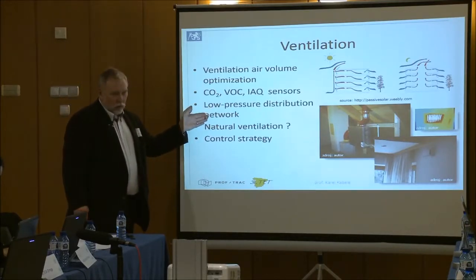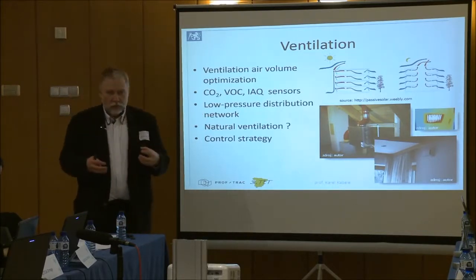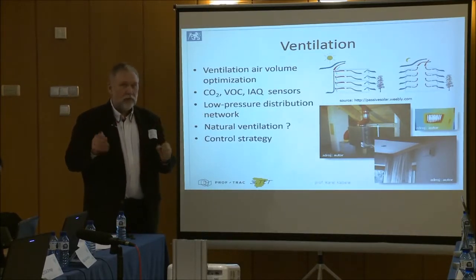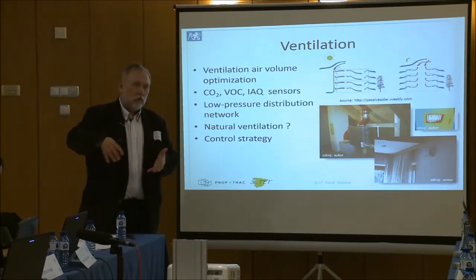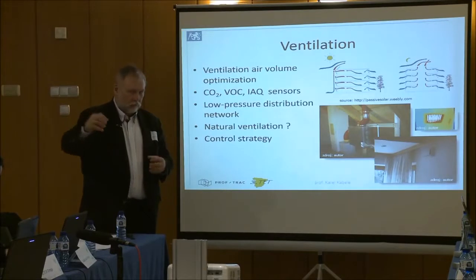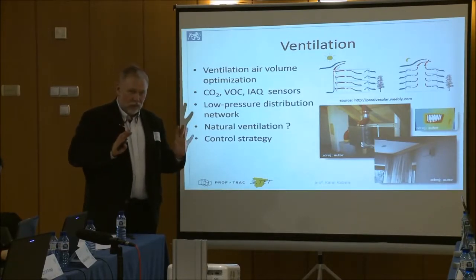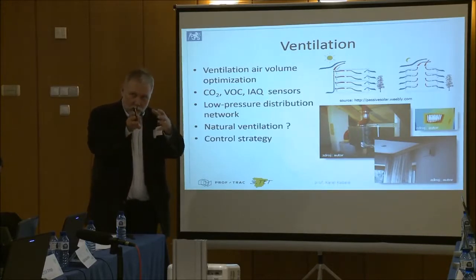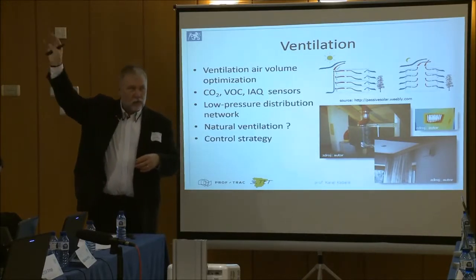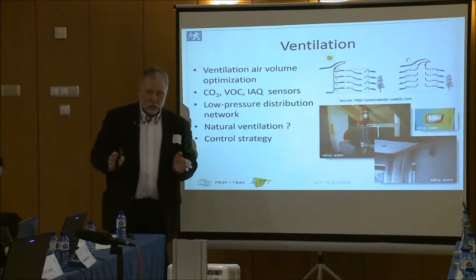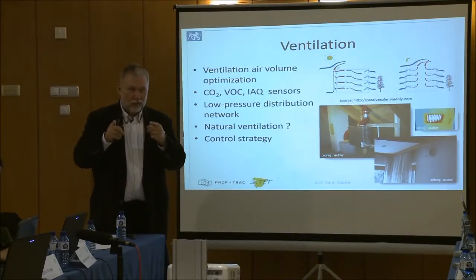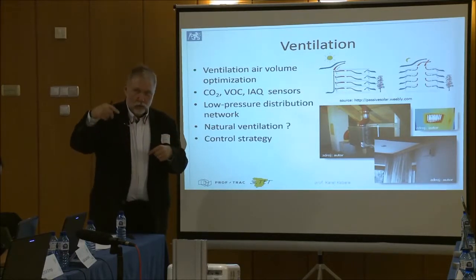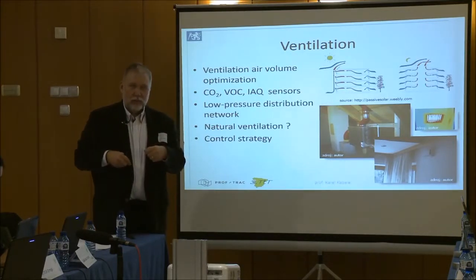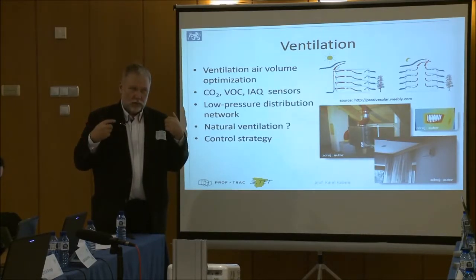Low pressure distribution networks - there's a big movement now to not have pipes for ventilation and instead use corridors and rooms to transport fresh air. No problem, it's possible - we use air from this room, transport it to the corridor, and exhaust it somewhere on the other side of the building. That's no problem, but we should create openings for that air - air from this room should be able to get into the corridor behind the door, so we need openings. But at the moment we're facing problems with acoustics and with fire protection.